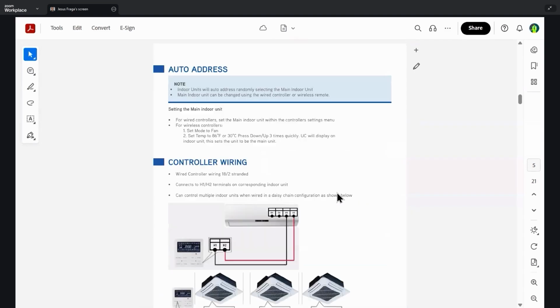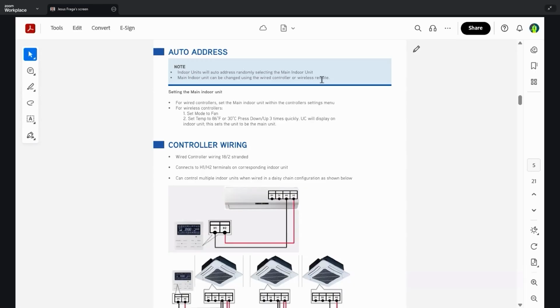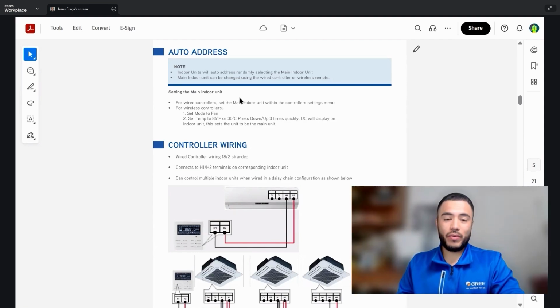So going on. For auto addressing, it's a lot similar to the 14A models. The indoor units will auto address, randomly selecting the main indoor unit. Main indoor units can be changed using the wired controller or wireless remote. So what this means is you can actually go into the wired controller, before you go through the commissioning, and designate what address you want for what area.